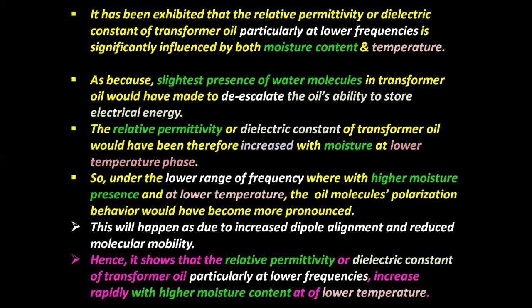The relative permittivity or dielectric constant of transformer oil increases with moisture at the lower temperature phase. So, under the lower range of frequency, where there is higher moisture presence and lower temperature, the oil molecules' polarization behavior becomes more pronounced.